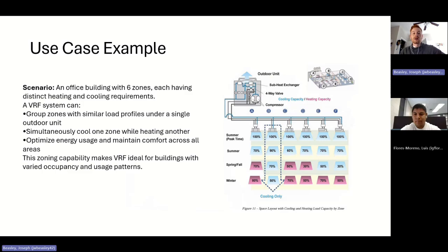So one example you can think about in this scenario, consider an office building with 6 different zones, and they each have different heating and cooling requirements. So the boss likes his office very cold, but the other person does not. So with VRF, you can group the zones that have a similar profile. If all the rooms are under a similar temperature and they're being loaded a similar way, you can pipe all of those to a single outdoor unit. So you can save some electricity that way. And you can simultaneously cool one zone while heating another. This can optimize energy usage, and it maintains comfort across all areas so that people can be comfortable no matter which space they're in. And this capability makes variable refrigerant flow ideal for buildings with varied occupancy and usage patterns as well, because you can turn it off when there's not as many people there.